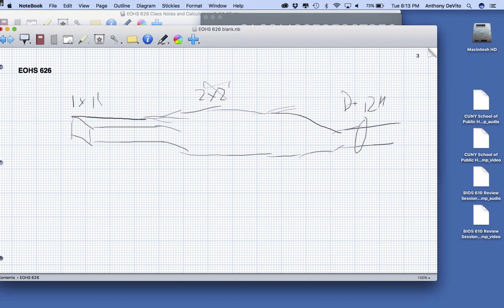I'm going to tell you that the quantity of air Q going in here that we need to move is 2,000 CFM, cubic feet per minute. So tell me, what's the velocity here? What's the velocity in this circular duct down here? Okay, so we've got Q equal to V times A. Or in other words, since we're really interested in the velocity, why don't we just use the formula V is equal to Q over A?